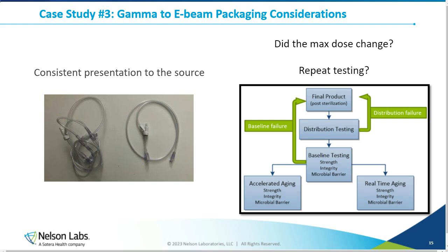The problem with the spaghetti tubing here in my picture on the left is that density in one area is really low, but it's really high in another area. And if I have loose packages inside of a box, they may shift around. Again, I don't have consistent density throughout the box as it's being presented to this source. The picture example on the right is a much better one, where the tubing is coiled so that it's all monolayer. Then you would also need something to keep that in place, whether it's a tray or some kind of a clip insert that holds it all in place, as long as you can keep it all uniform so that every time it goes under the E-beam source, the E-beam is getting exactly the same product every time.